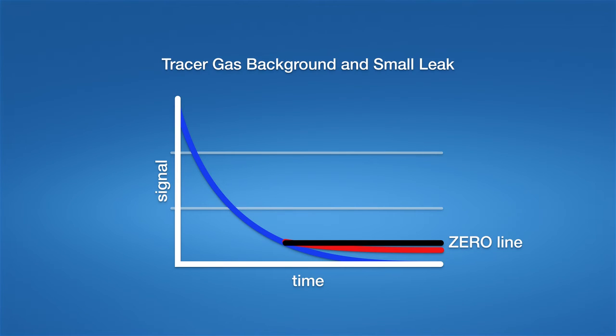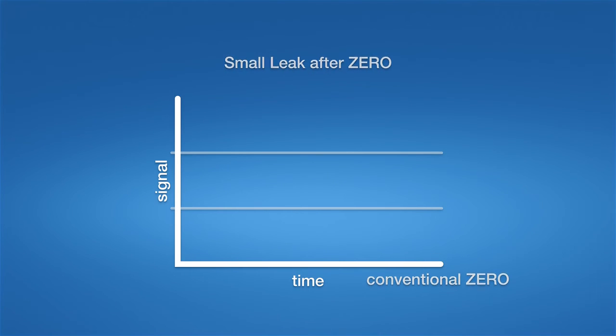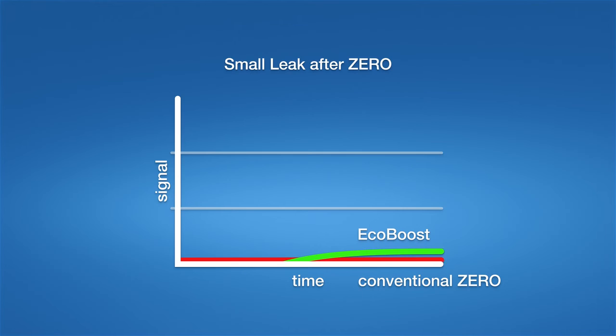Therefore, a conventional zero function will not show any signal if the red curve is not increasing. But we know that our true leak signal is the difference between the blue curve and the red curve. Again, the new EcoBoost is able to predict the blue curve and display the true leak size instead of pretending that there is no leak at all.